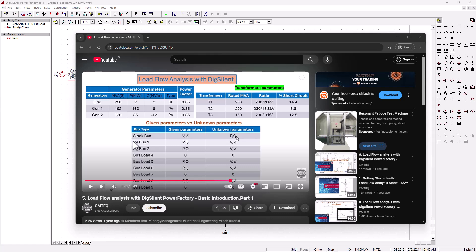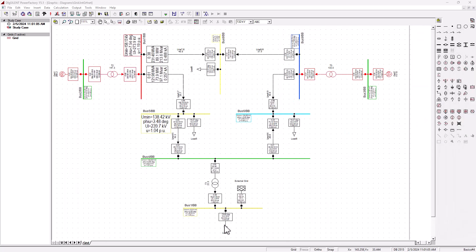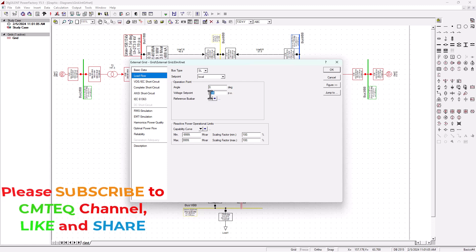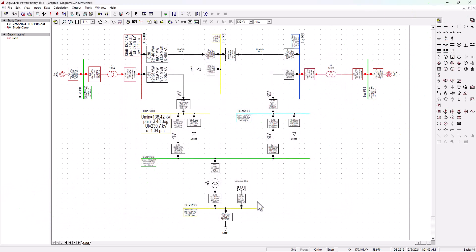As specified previously, for the slack bus, the given parameters are the voltage and the angle, which is sitting at zero degrees, and the unknown parameters will be P and Q. When we head over to the external grid and double-click on the load flow analysis, we can see that the voltage set point is at 1.04 per unit and the angle is zero degrees. These are the given parameters for our slack reference bus. The unknown parameters, which are P and Q — the real and reactive power pulled out of this bus — will be determined after running the load flow analysis.